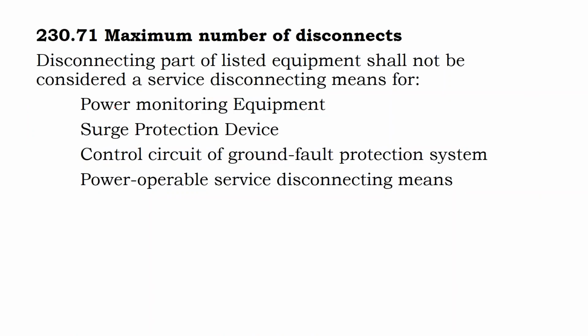Your service panels are the same way. You can kill power to the panel at the switch and kill power to the whole panel, but you still have hot power coming into it. So that external disconnect switch requirement is there so that you can have people accessing the equipment and servicing it without electrocuting themselves. And eventually that safety issue makes another appearance on your main service panel.